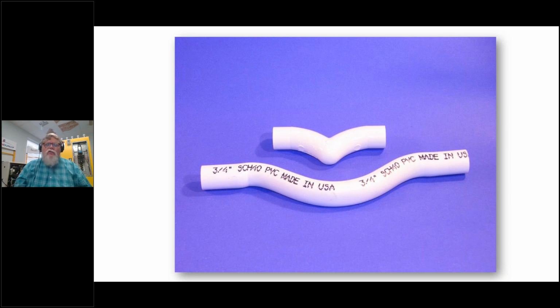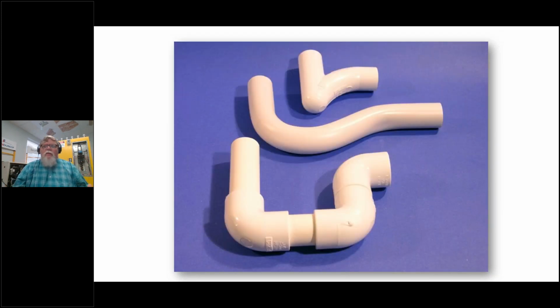The traps themselves, we refer to them in the business as running traps. They tend to not be real good. I mean, they kind of work sometimes, depending on the static pressure in your duct system and so forth. But a lot of times when a system starts out, it can actually suck the water out of the trap, and until the unit shuts off, the water doesn't go back into the trap and reprime it.